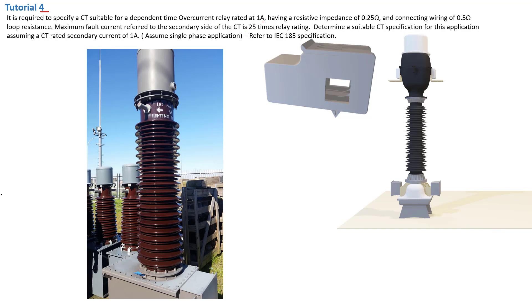The relay is rated at 1 amp, having a resistive impedance of 0.25 ohm, and connecting wiring of 0.5 ohm loop resistance. Pay attention to the problem statement. The maximum fault current referred to the secondary side of the CT is 25 times the relay rating. Determine a suitable CT specification assuming a CT rated secondary current of 1 amp, which is the same as the relay rated at 1 amp.